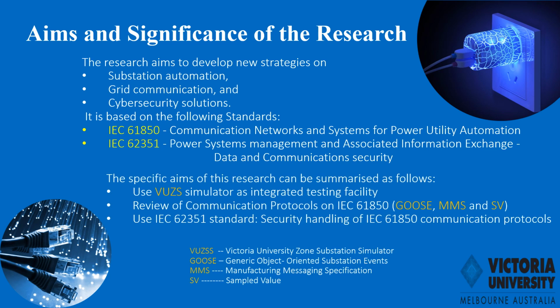The specific aims of the research can be summarized as follows. We could use the VUZS simulator as an integrated testing facility for other power utilities who want to simulate for research purposes. The other one is the review of communication protocols on IEC 61850, we have the GOOSE, MMS, and SV. These are the acronyms used for the entire research and presentation. The use of the IEC 62351 standard is for security handling of IEC 61850 communication protocols.